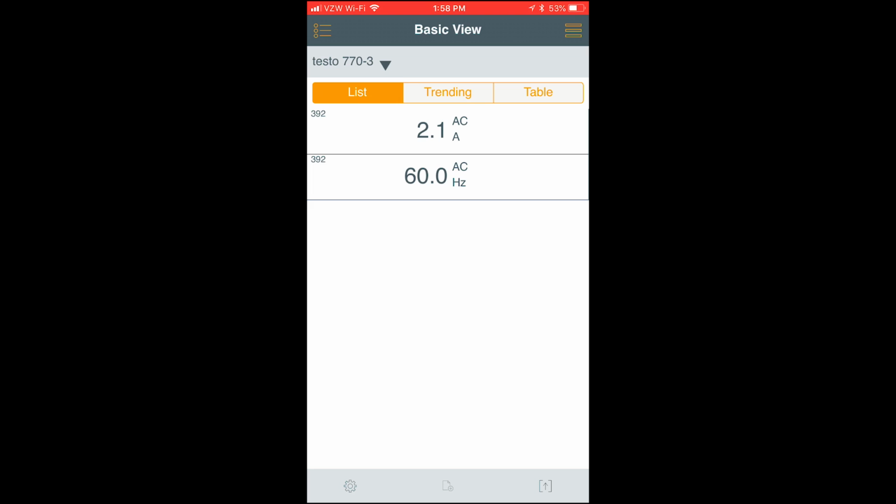All right, so our blower is drawing 2.1 amps at full load, 0.4 static, and we are rated for 0.5 on this one on the data tag. Full load amps is 4.3, so all is well. All's well that ends well.